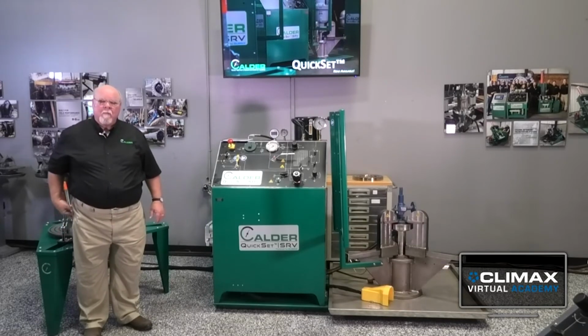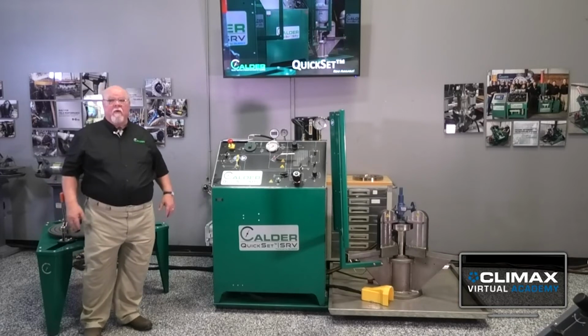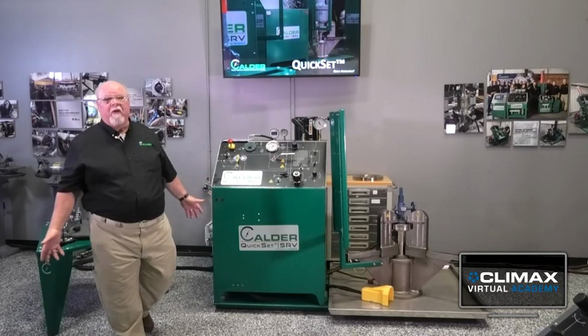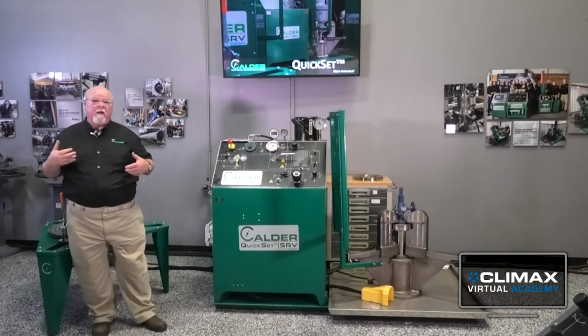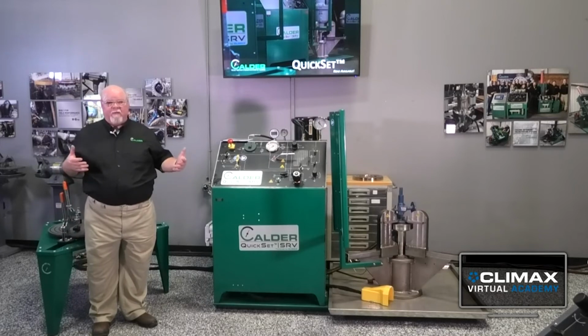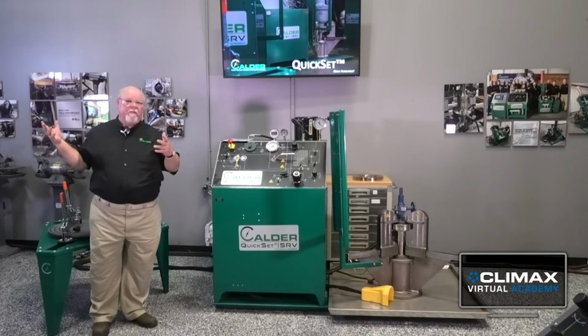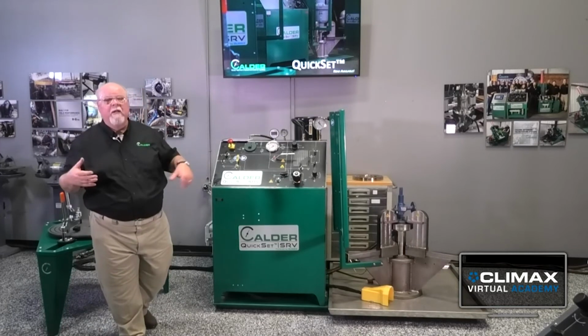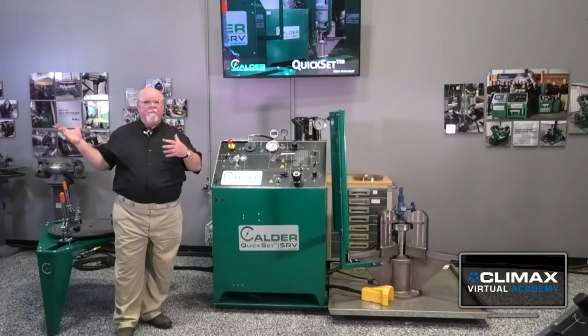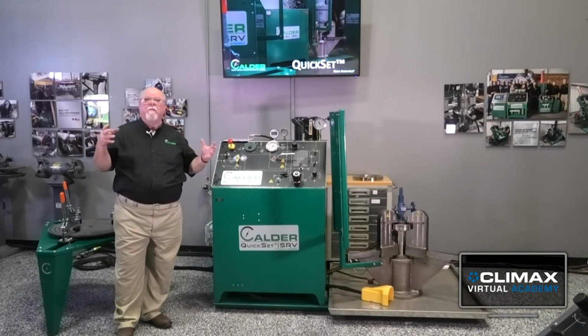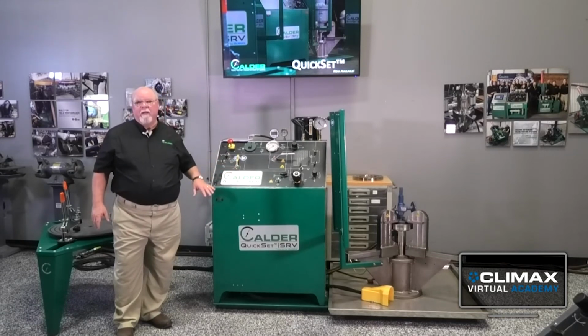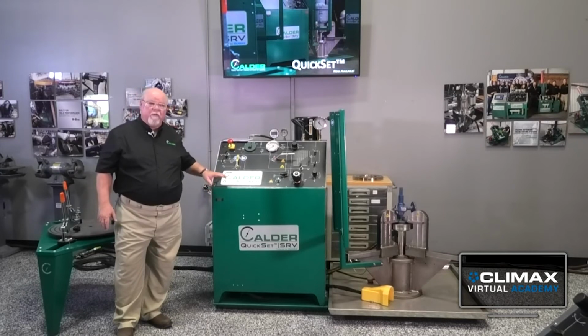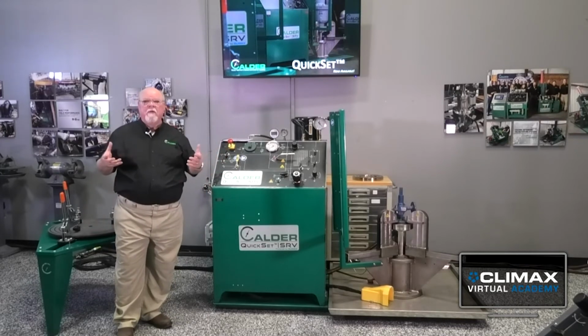What high pressure test source options does Calder offer? The question is what high pressure test sources does Climax or Calder offer as an option. Again, it's a shop environment: a 6,000 psi compressor with bottle accumulation stored that can feed. The customer can always rent, or if they have nitrogen bottles themselves or compressed air, they can use those directly. For field use, we also offer a booster style pump, like this unit is set up with, that allows you to take just standard 100 psi shop air or compressed air from a portable compressor, build that pressure up and test as well.